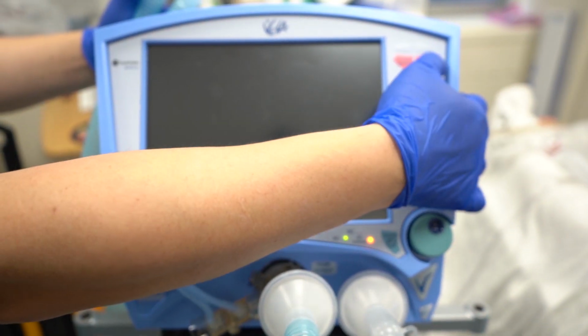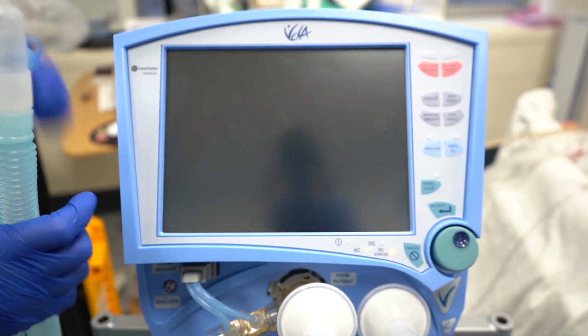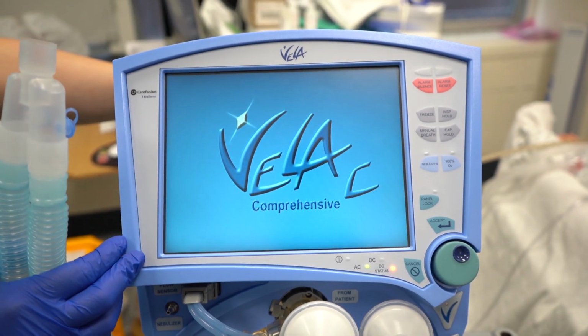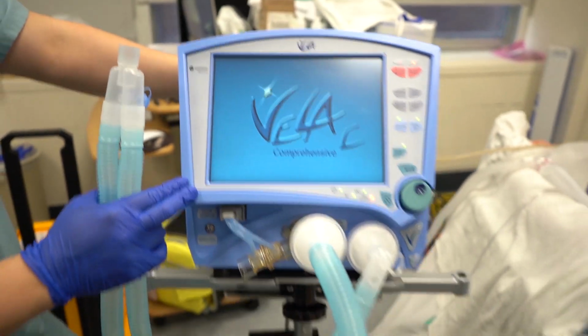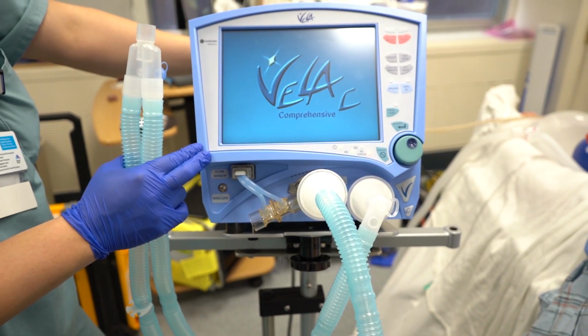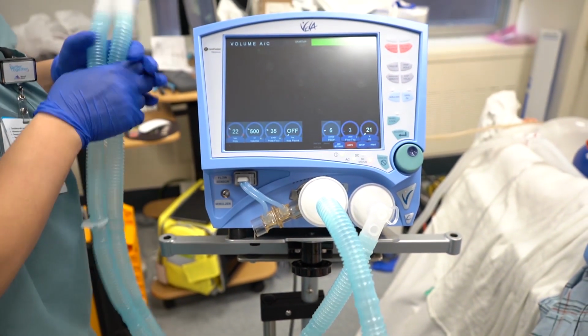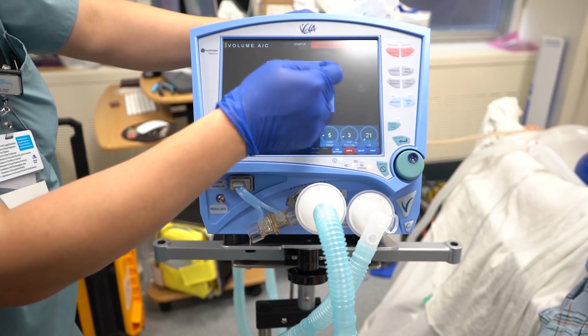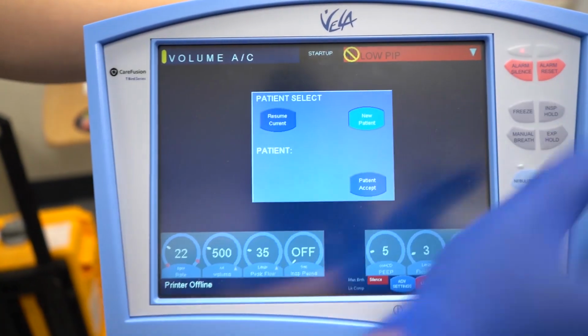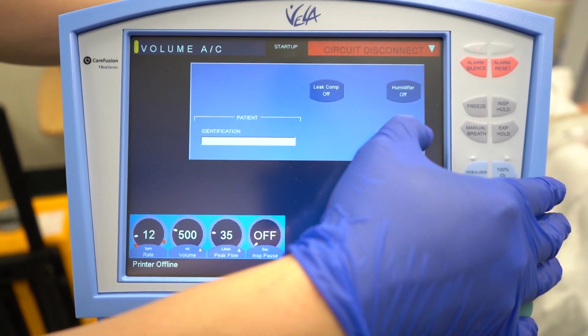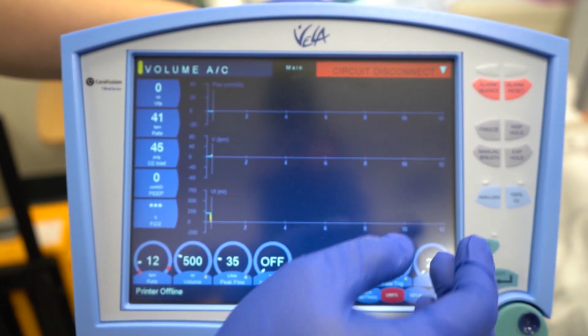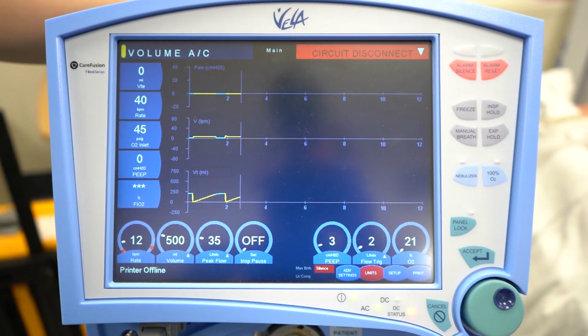Okay, so it passed. Once it passes, you just hit exit. It'll shut off and restart. And once it restarts, it actually goes straight into ventilation, so you can select resume current patient, or you can select a new patient. Okay. Once you hit new patient, patient accept, you can bypass this, just hit setup accept. There's a leak comp if you need it, but we usually don't use it.